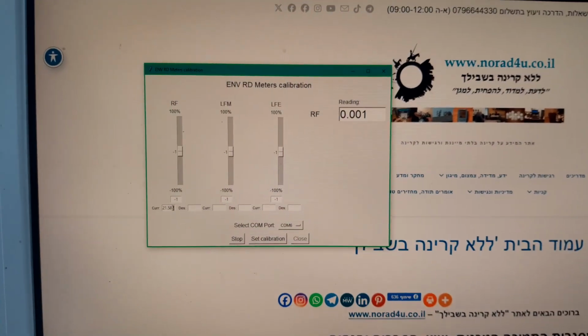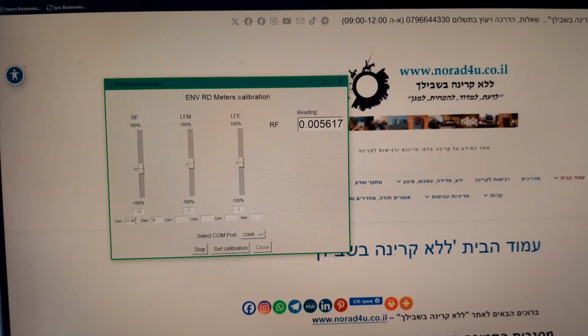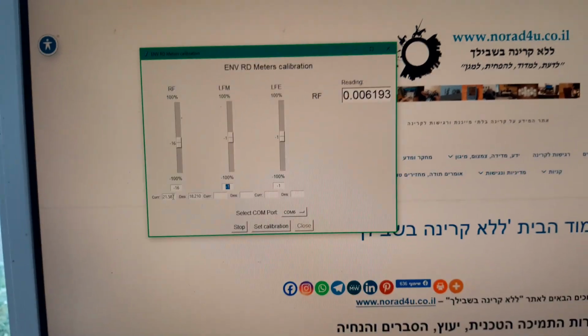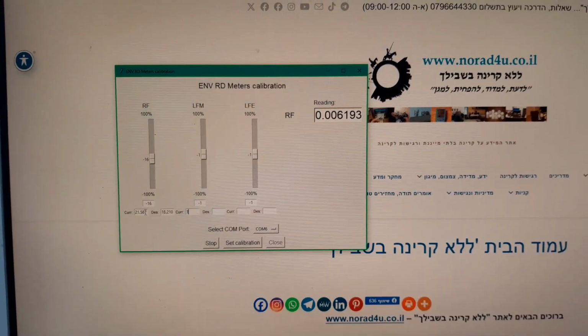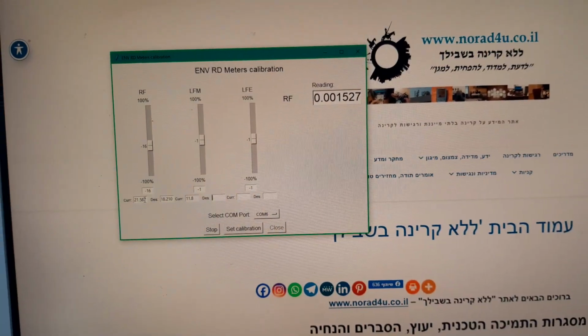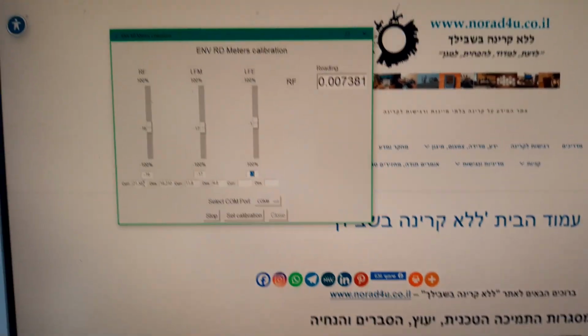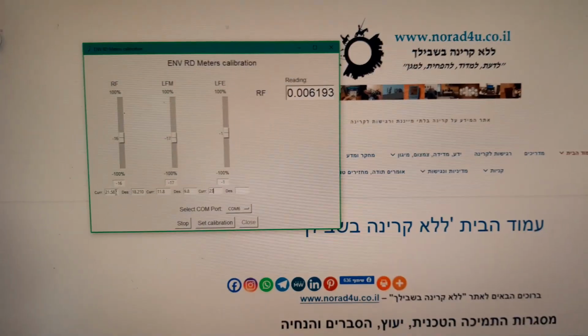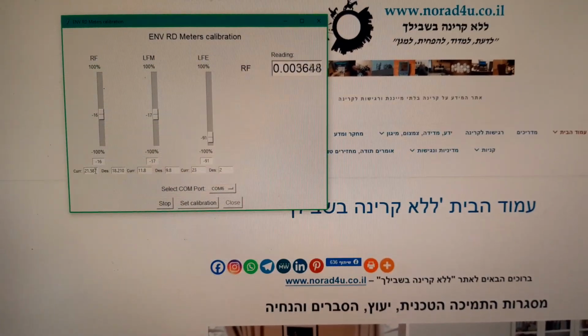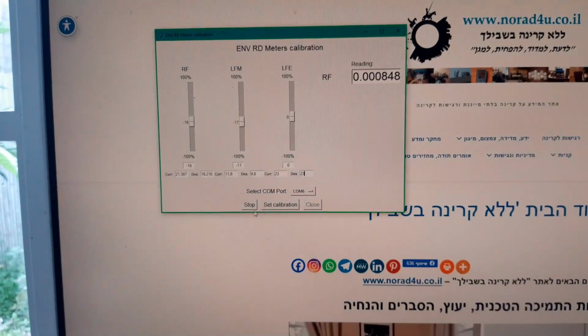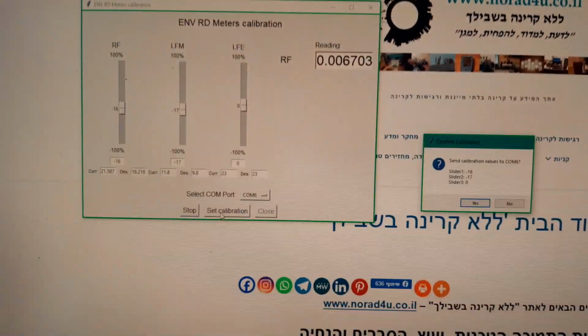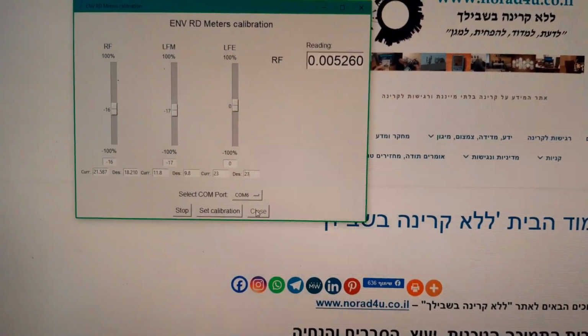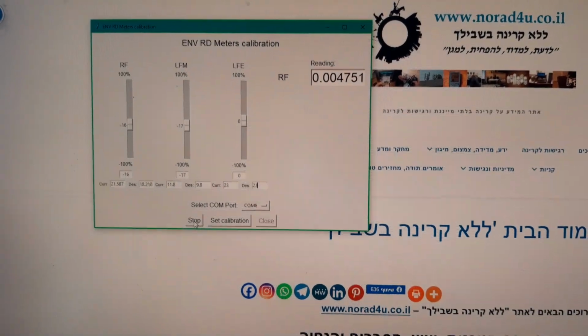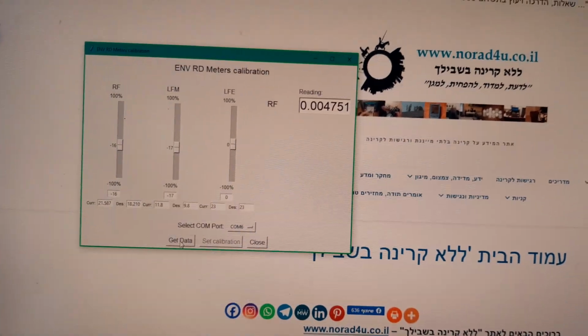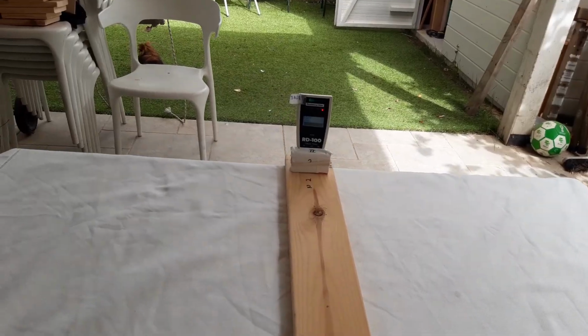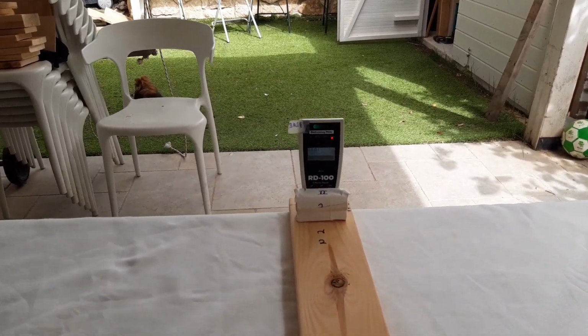And I'm punching in the values I saw on the unit under testing and the values that the reference meter showed in every one of the fields, in RF, in low frequency magnetic, and low frequency electric. And the software calculates the calibration factor that needs to be sent to the meter in order to get the outcomes closer to the reference meter. I send the data to the meter and it's saved. Now I will redo the testing in order to make sure that the calibration factors are correct, and the meter is now measuring very close to, or closer to, the reference meter, sorry.